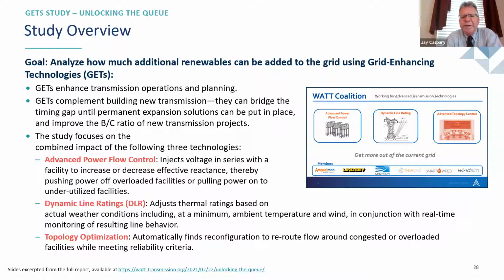We also looked at dynamic line ratings, a way to get more accurate ratings of transmission lines based on actual conditions, the biggest factor being wind speed. In the models we used, we had real 2019 and 2020 data, so we knew the wind conditions throughout the system. We made conservative assumptions about wind direction and speed, limiting the ability to push more power down existing lines to about 20%, which is very conservative based on actual operations and research. The latest research I've seen shows that over a 2-year period, DLR can actually increase the capacity of transmission lines by about 30%, which is tremendous.